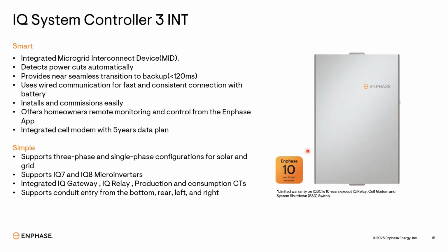Now coming to the IQ system controller. This is a part of your complete Enphase energy system. If you are going to install batteries, you need to install a controller also. So what is this? Basically, it's an integrated microgrid interconnect device. It's a MID device. It creates a microgrid once there is no power inside your home. It detects a power cut automatically, and it provides a seamless transition, which is less than 120 milliseconds. It uses wired communication with CAN cables for faster communication between batteries and the inverters and controller. We do not rely on wireless communication because it is weak. Wired communication is faster.